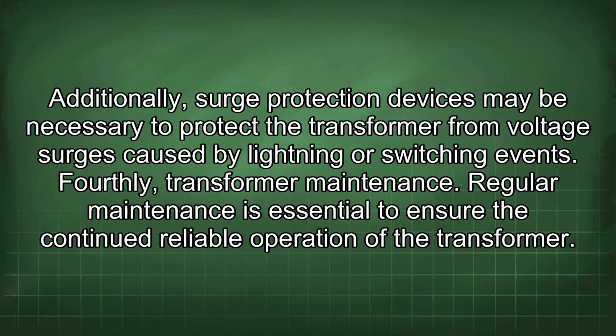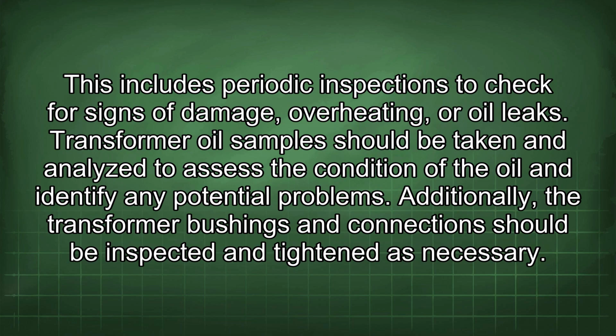Fourthly, transformer maintenance. Regular maintenance is essential to ensure the continued reliable operation of the transformer. This includes periodic inspections to check for signs of damage, overheating, or oil leaks. Transformer oil samples should be taken and analyzed to assess the condition of the oil and identify any potential problems. Additionally, the transformer bushings and connections should be inspected and tightened as necessary.